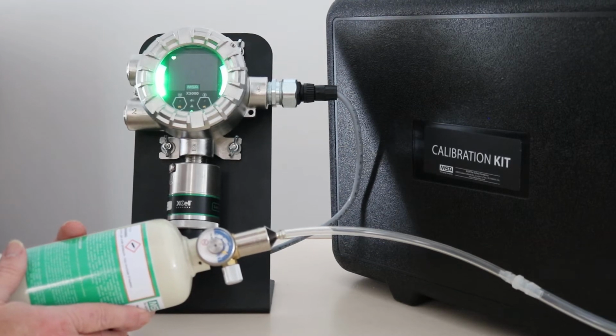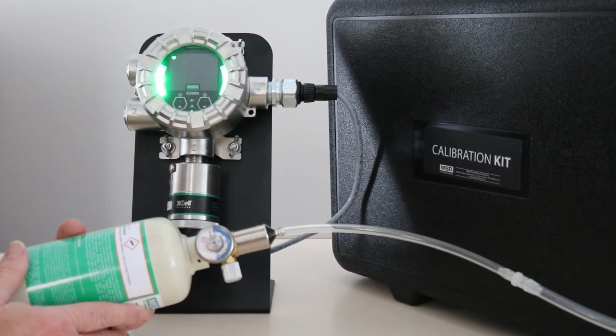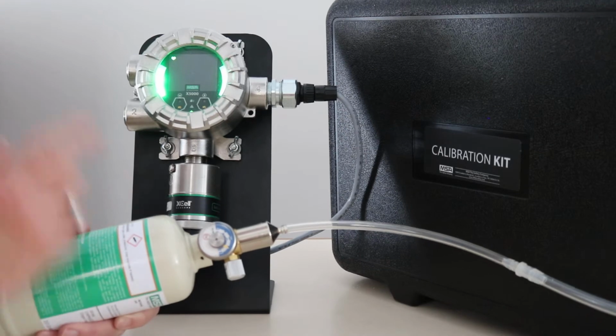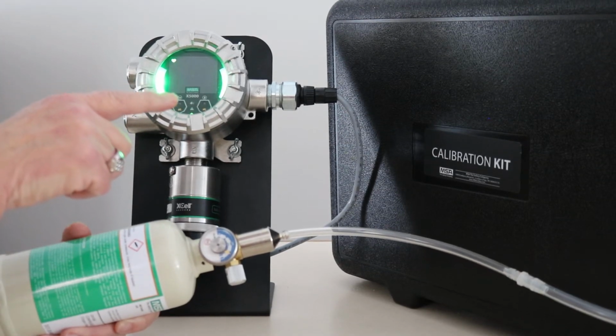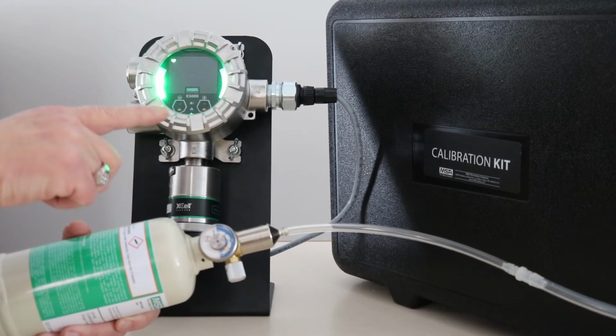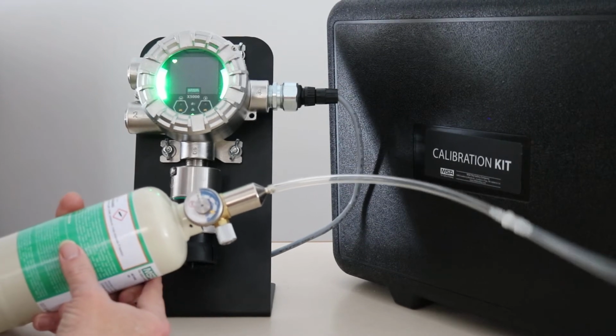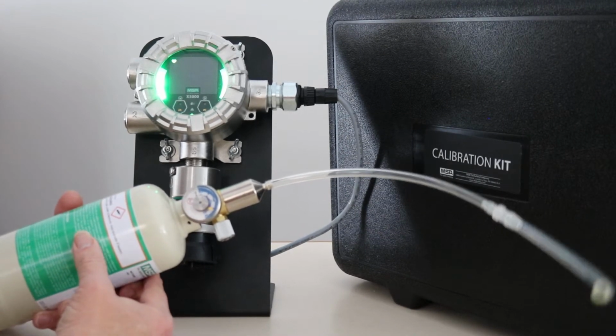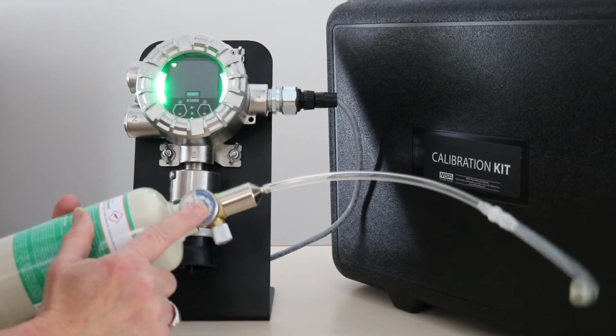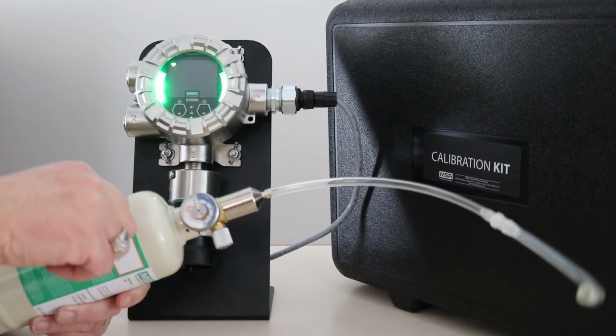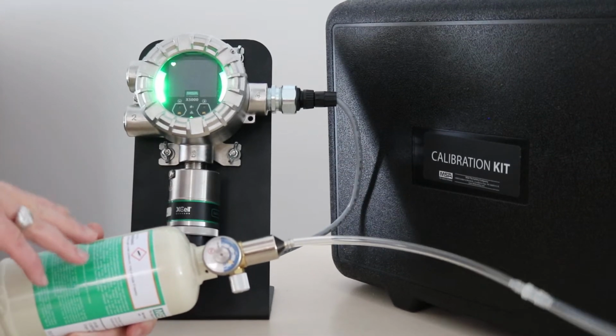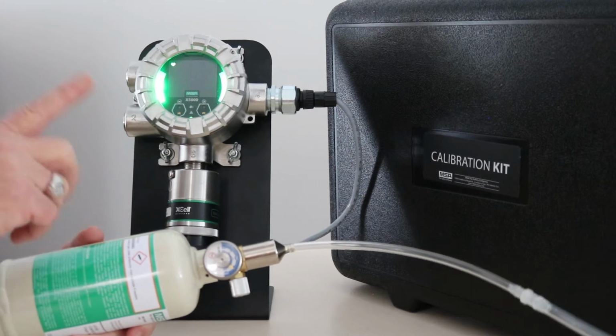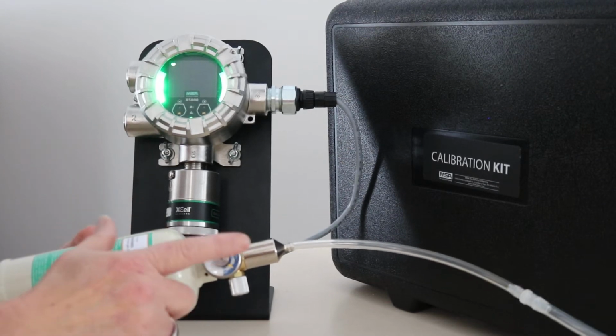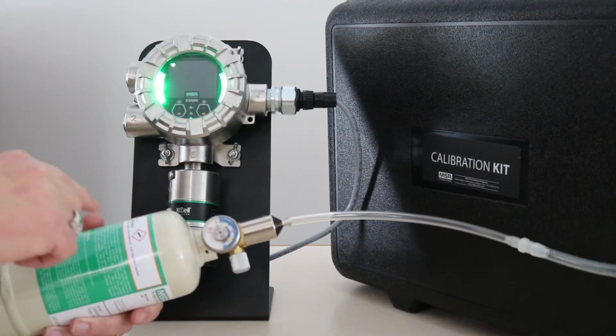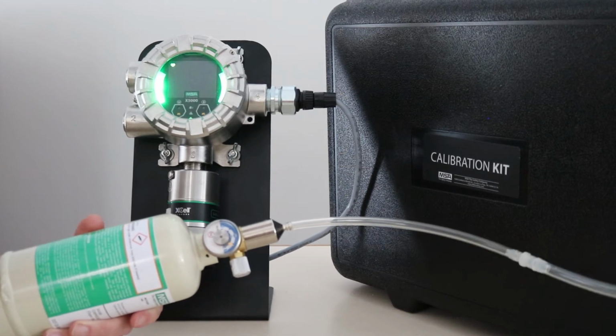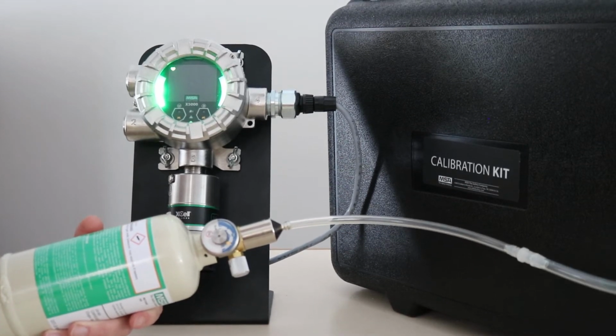So in this case, we have a demo of the X5000. The first thing you'll need is a calibration kit. When you order a calibration kit, you'll get a plastic carrying case like you see over here, and your span gas or zero gas cylinder, your regulator, and the tubing. You can just order your zero gas in a cylinder only and use the same regulator and tubing. However, I suggest you don't, and you'll see why when we get into the calibration.